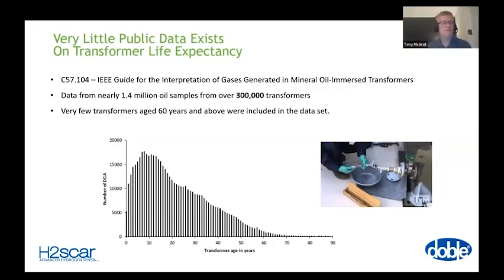I would like to go back to something Moses said about qualified workers. It's relevant here that to take a good oil sample, to generate data, to assess the condition of your transformer, and then make a decision about that transformer, needs someone who knows what they're doing to take a sample. Not only are they qualified to be on the site, not only are they qualified to take a sample, but when they take a sample, or run an SFRA test, or run a PD test, can they recognize data which is acceptable? Irrespective of how you interpret it, can you actually recognize that you've made a good reading before you try to work out what the reading means? That to me is what a qualified worker is - they can identify an SFRA trace and say, yeah, it's what we'd expect. Now we'll try and interpret it.